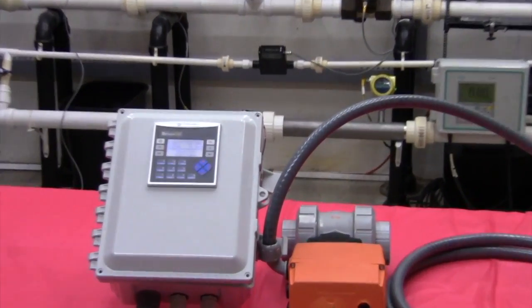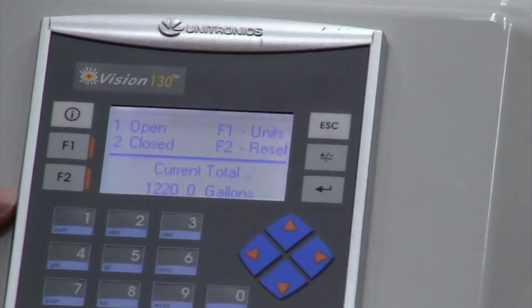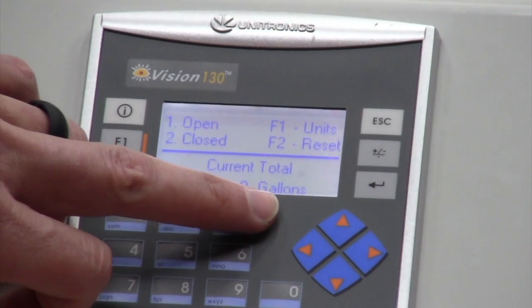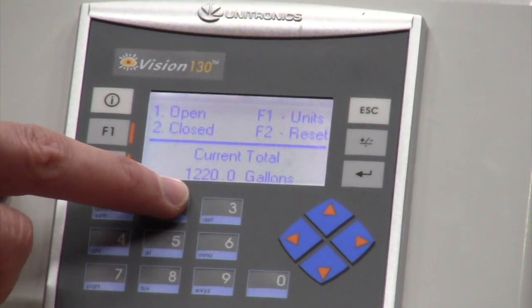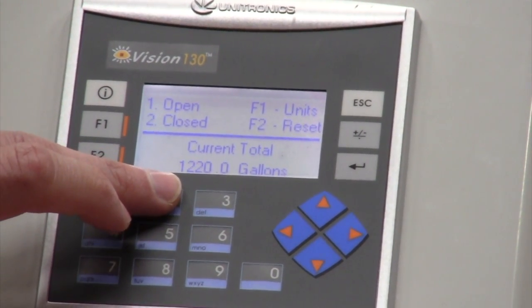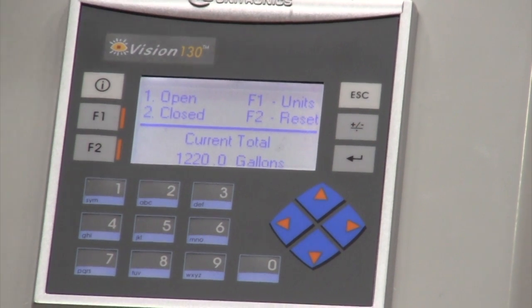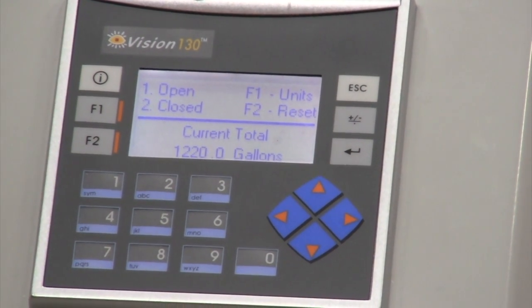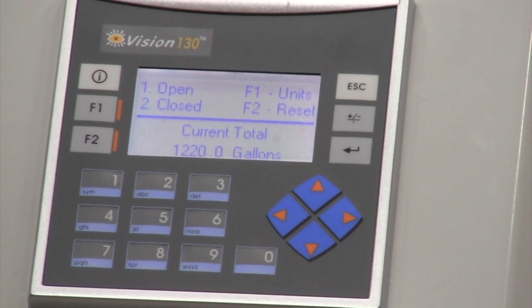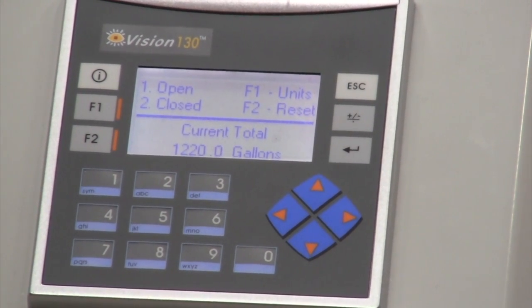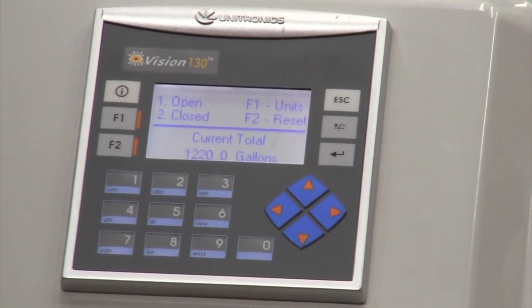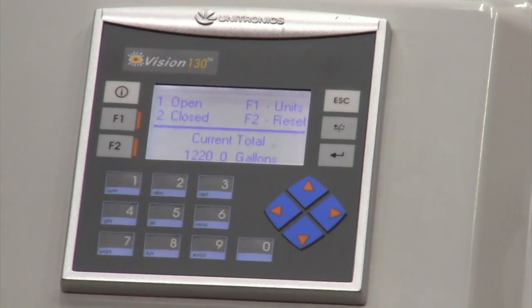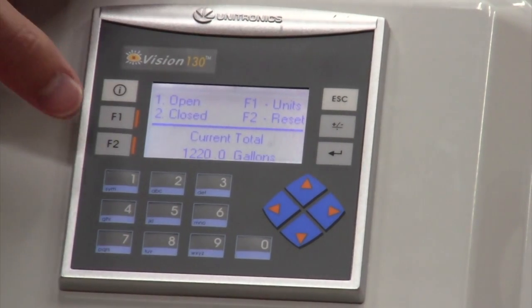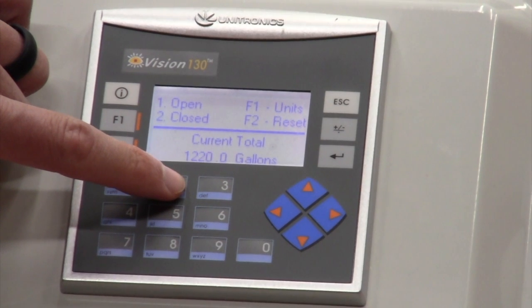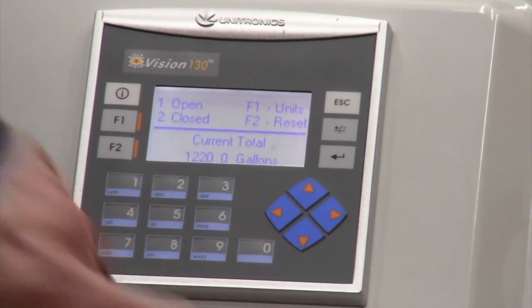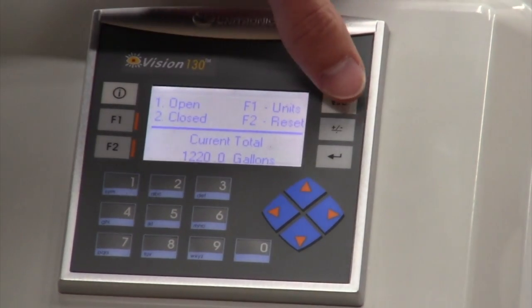Come back over to the display, and we're showing a total of 1,220 gallons on the display. But since our K factor is set to 1, that's actually raw pulses. So since I have a 5-gallon bucket, I simply take 1,220, divide it by 5, and that will give me my K factor. That comes out to 244. So I need to hit number 2, that closes my valve.